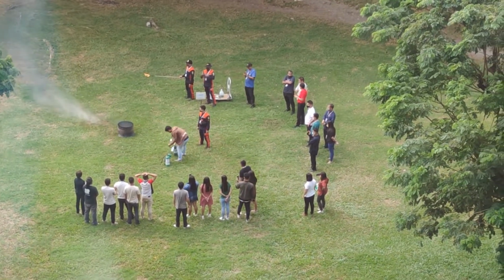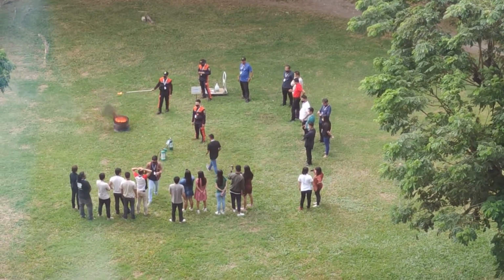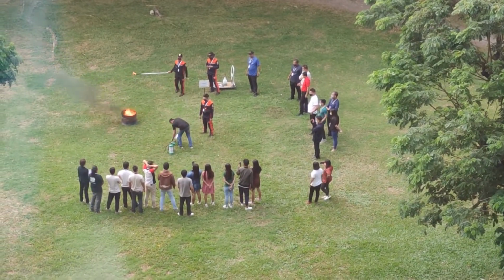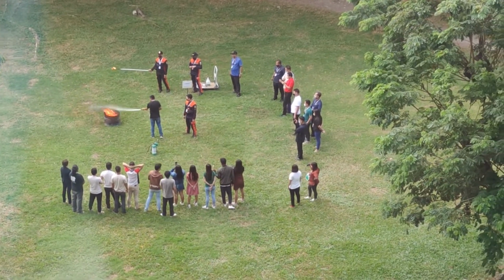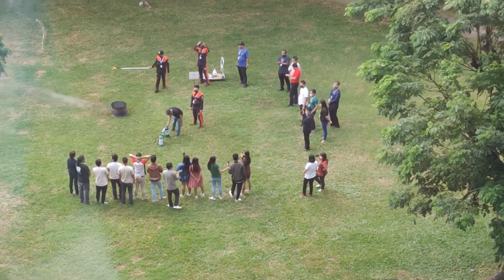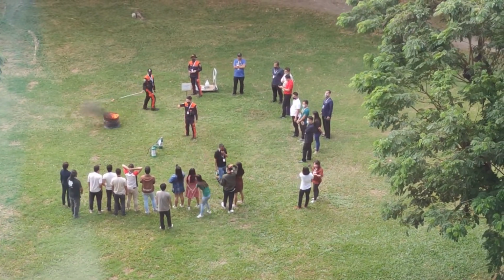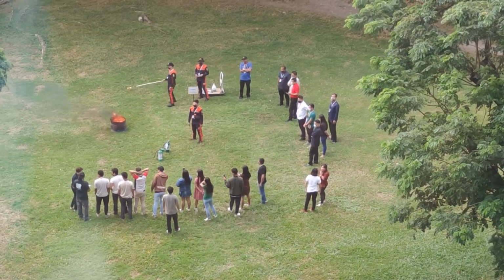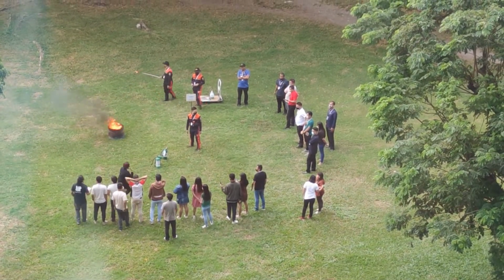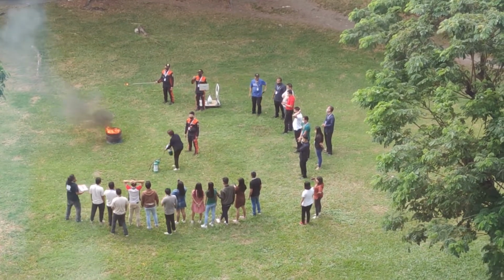Fire extinguisher maintenance. Fire extinguishers should be regularly checked to ensure the following. The extinguisher is not blocked by furniture, doors, or anything that may limit access during an emergency. It is properly mounted in the path of an exit and away from heat sources, and the pressure is at the recommended level. Your extinguisher may have a gauge that indicates when the pressure is too high or too low.